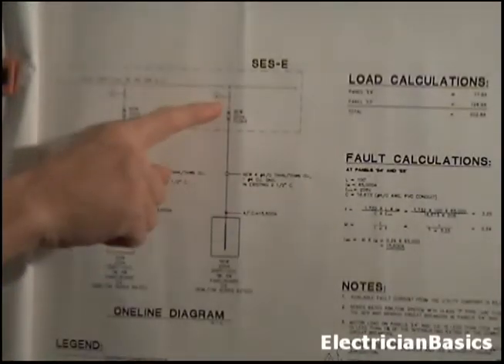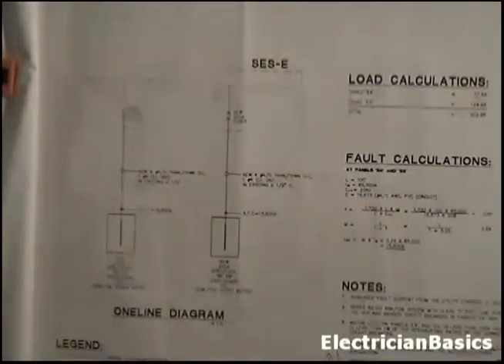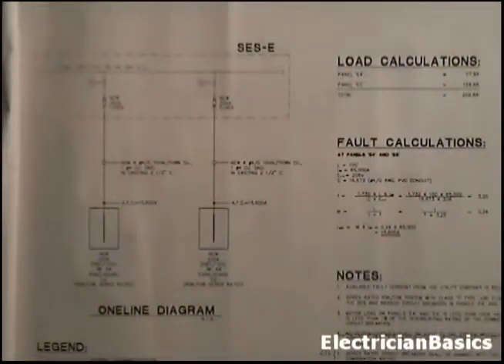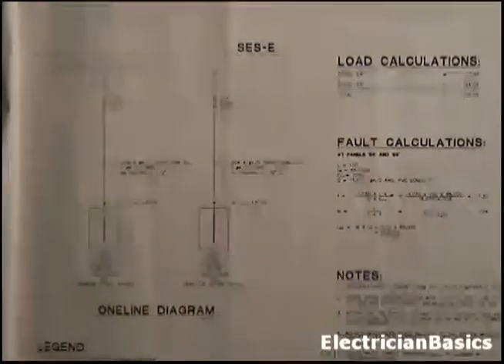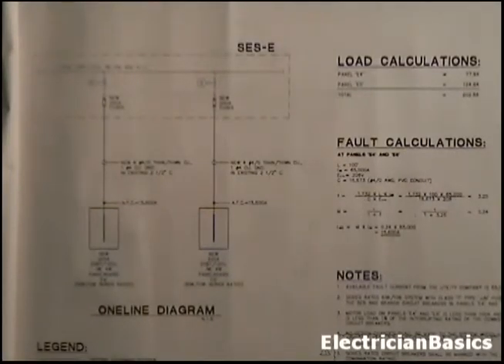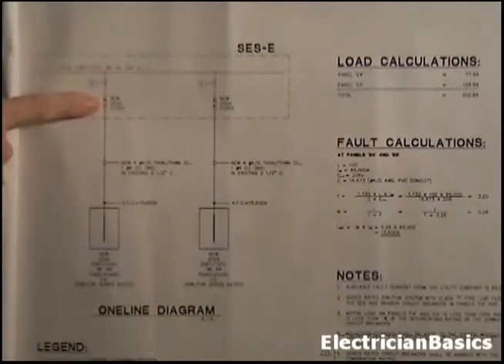Now this symbol for meter is not in your symbol diagrams on E0.1, but that's what that stands for. It's the meter. It may have been left off of the symbols because you are not installing that. The meter is something that the utility company puts in. From the symbols on sheet E0.1, which give the one-line diagram symbols, you can refer to those. Here we have a fuse, right here, 200 amp fuses, which protect the panel.